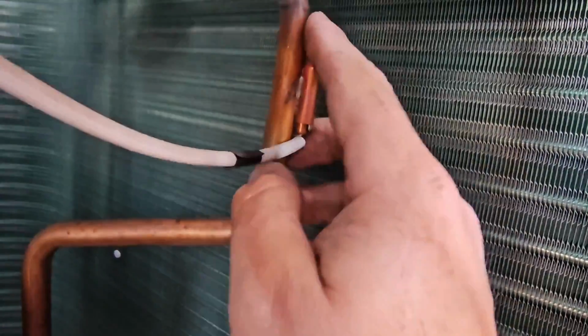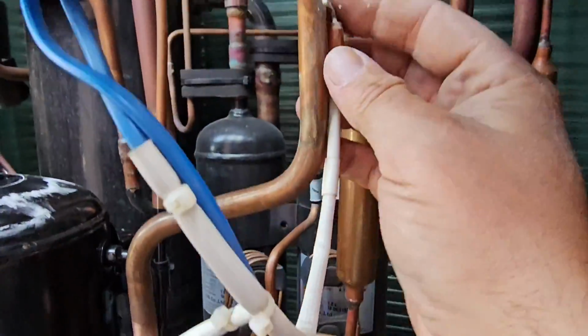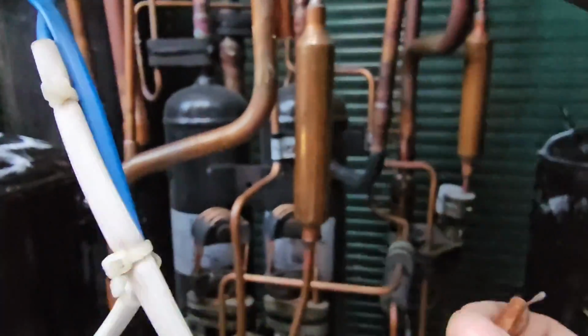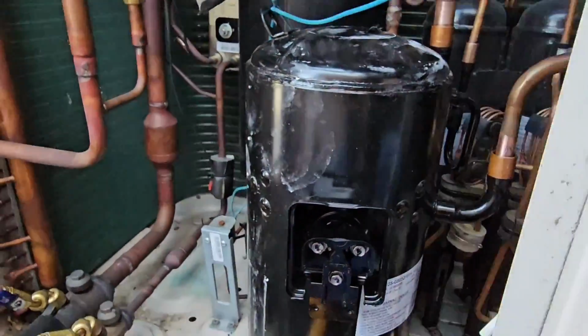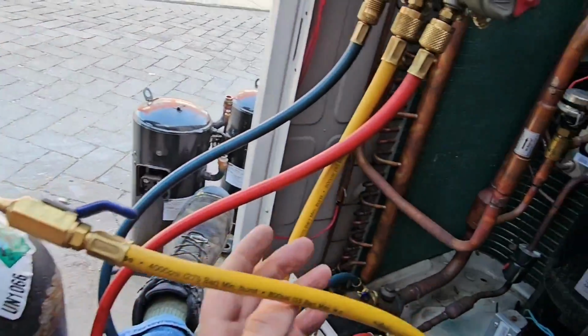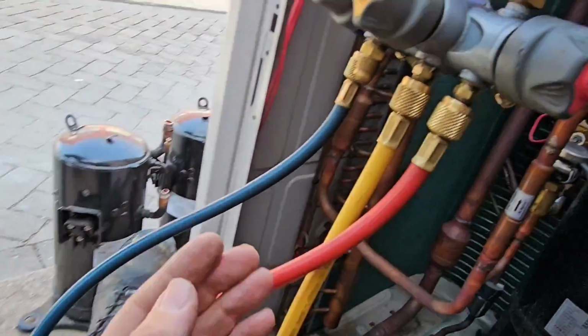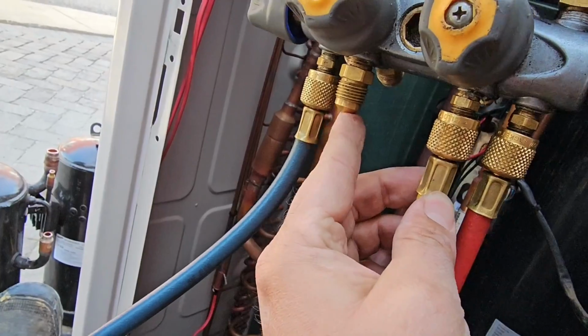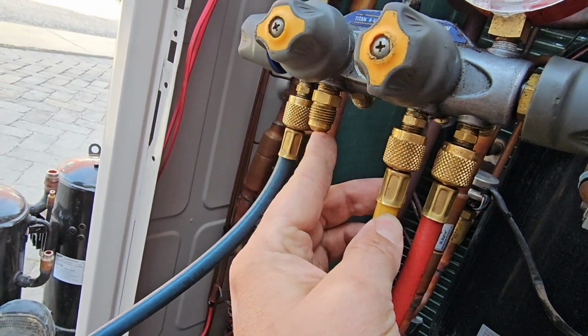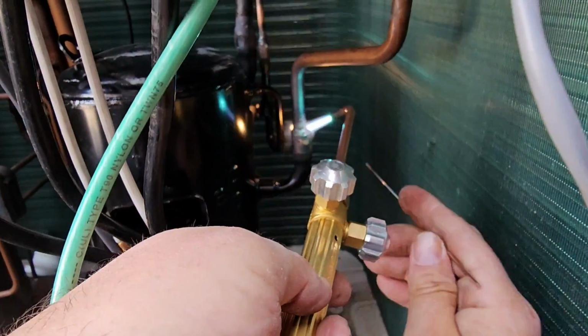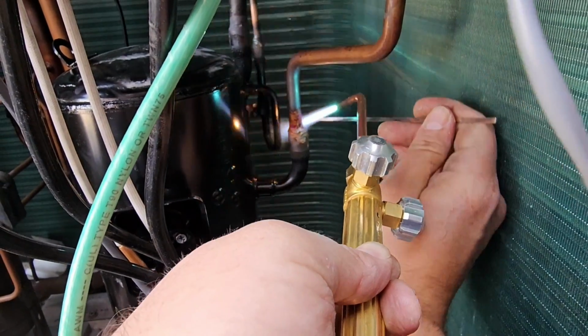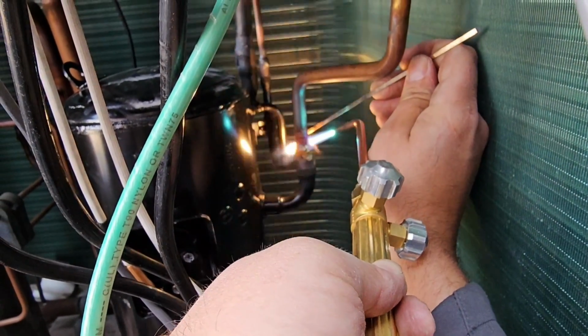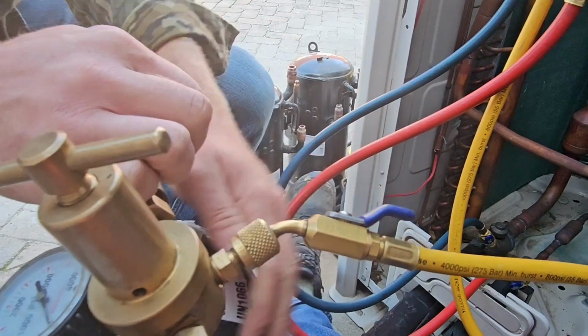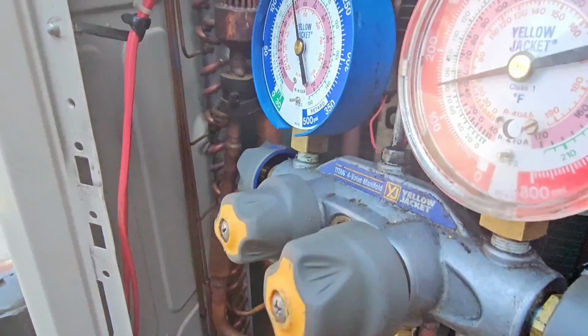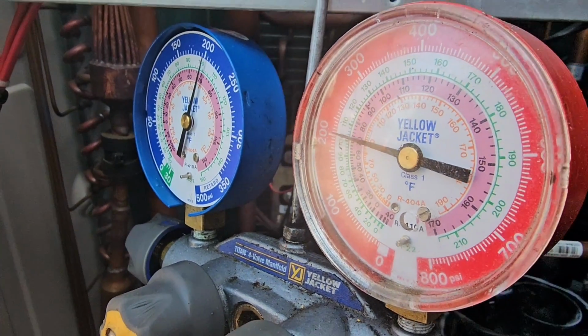Don't forget to remove the discharge sensor before you braze the discharge line. So, there we go. Forgot to bring the low flow regulator, so I've had to adjust this till I'm just barely pushing anything in. Adding some nitrogen so we can pressure test.